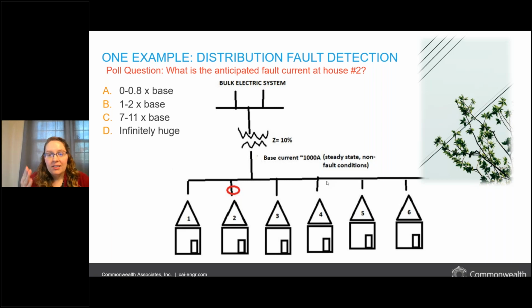So that means that current now has a path out of our system and into the ground. How many times of current do you think we will see in this fault or near the tree? That's the question I'd like us to consider here for a moment. So on a normal day, we'd see about 1,000 amps coming off of our transformer. But on a non-typical day, when the tree hits the distribution line, how many amps are we going to see entering that red circle area? Let's go ahead and launch the poll and see what your thoughts are on that.